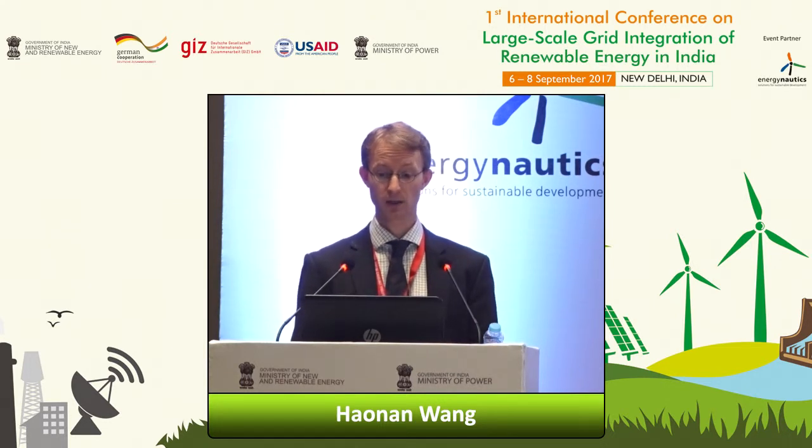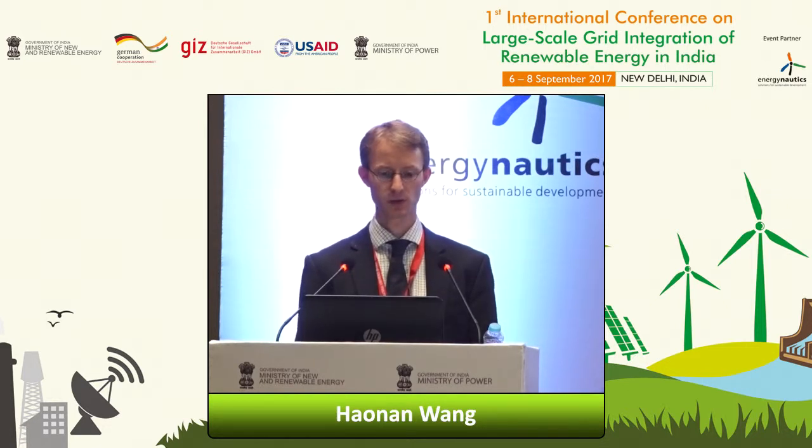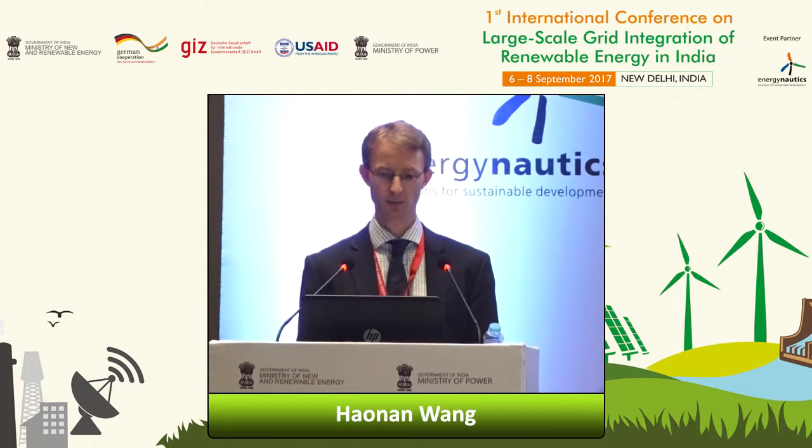We applied a simple concept to this case study region. We see there is a PV installation in low voltage, mainly PV installation in medium voltage, and high voltage, where we have quite a distribution of different types of generators. We used a methodology where we took active power time series of the installed systems, and based on measurements available over the former years, we applied different types of reactive power flexibilities of all the DGs with different limits. We are running annual simulations for that, going into a technical analysis.